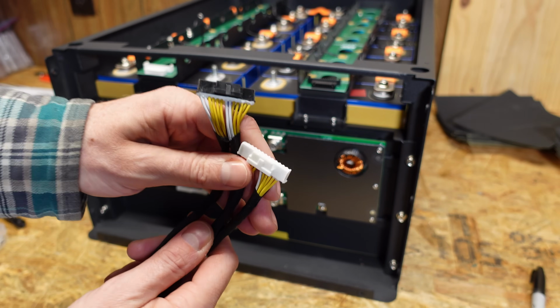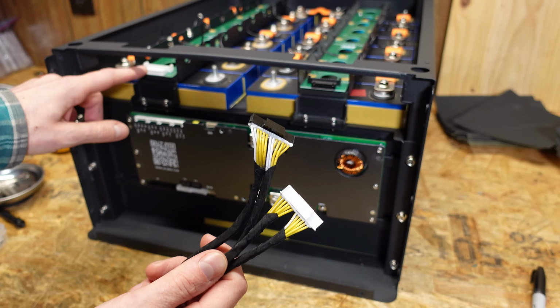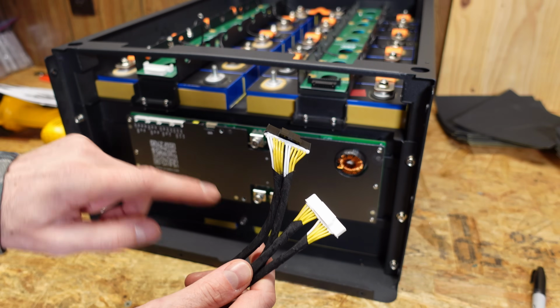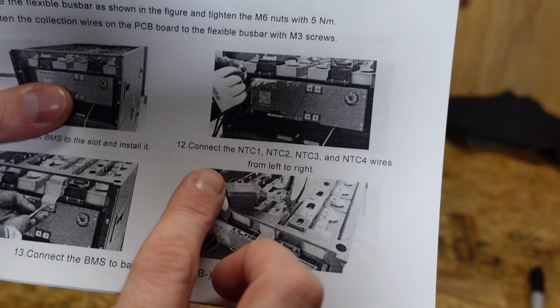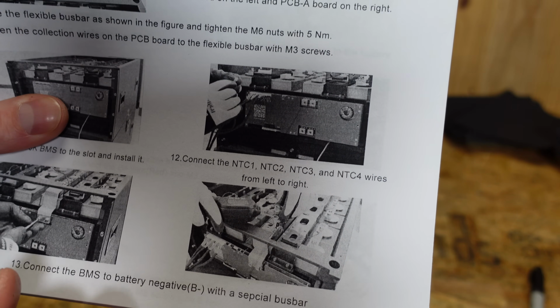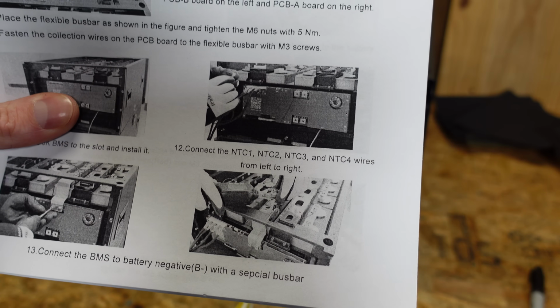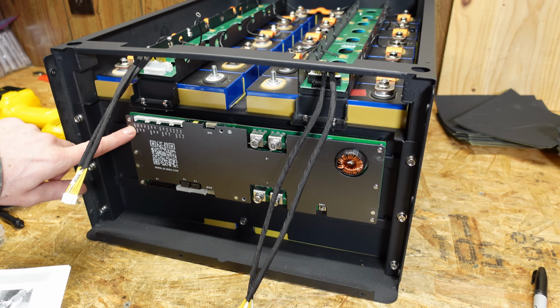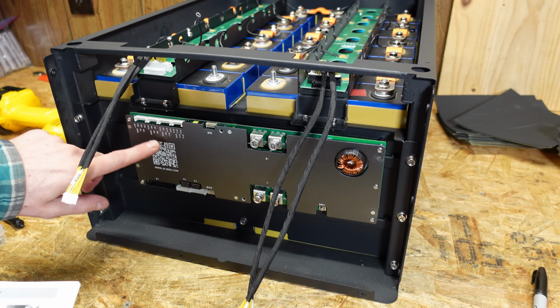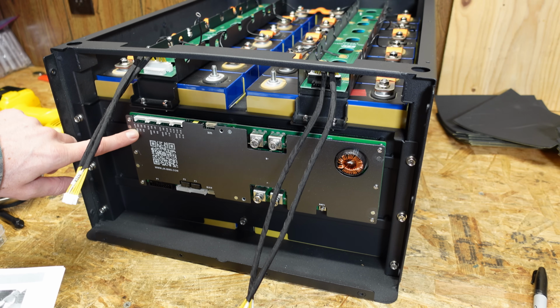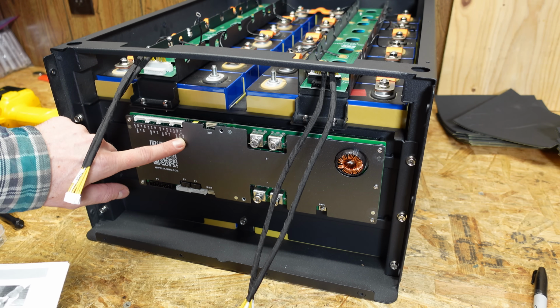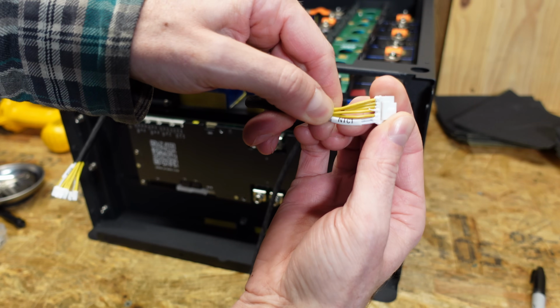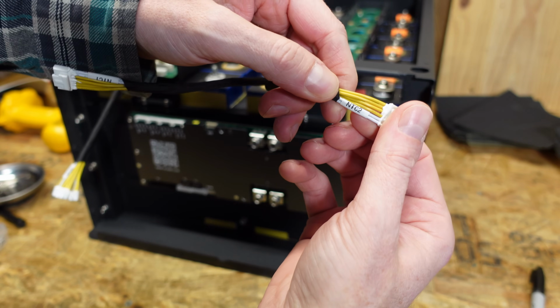So next we are ready to connect our balance leads. The black will go in the black connector over here, and the white will go in the white connector. Then the instructions say to connect them from left to right, which is the standard way to connect a BMS, starting with the lowest potential and working up to the highest potential. We can see on the left we are starting with B1 and we're working up to B16. These are labeled, so this says NTC1, and we have NTC2, and so forth.